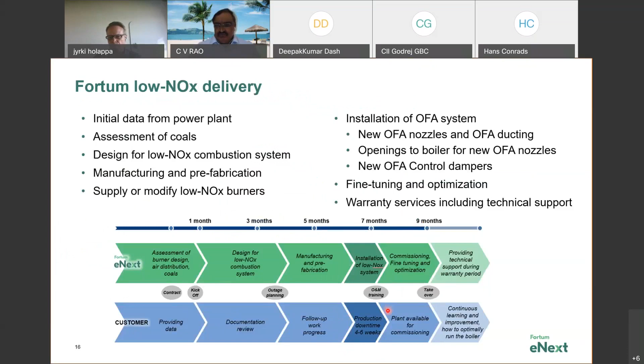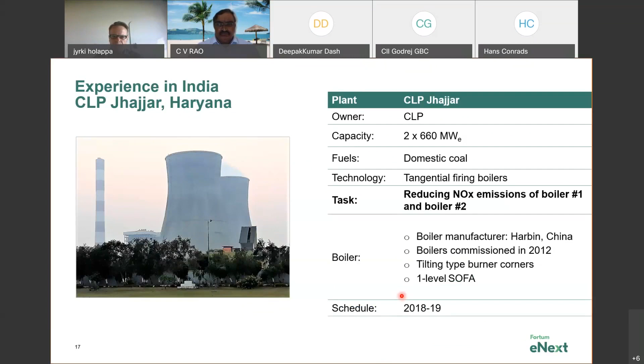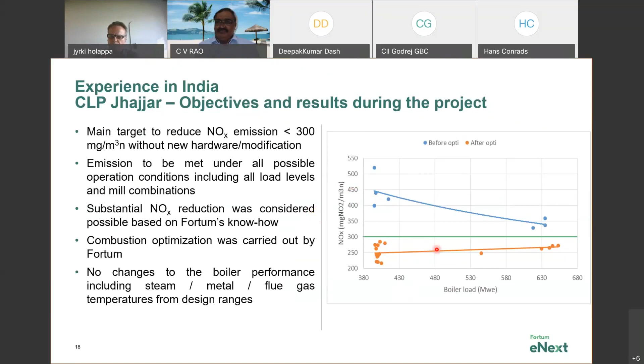We did boiler optimization work for CLP Jhajjar, which has two Harbin boilers. For them we carried out boiler combustion optimization without any hardware modifications, because this boiler was one of those rare cases that already had one level of SOFA installed, considering its age. The conclusion was that through optimization alone, we managed to reduce NOx levels to less than 300, and the customer confirmed after the project that they've fulfilled this 300 limit almost 100% purely through optimization.